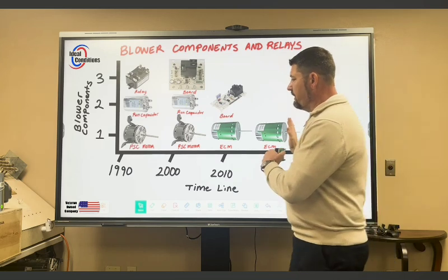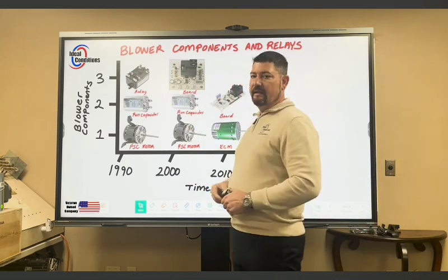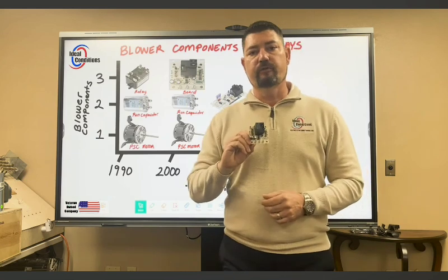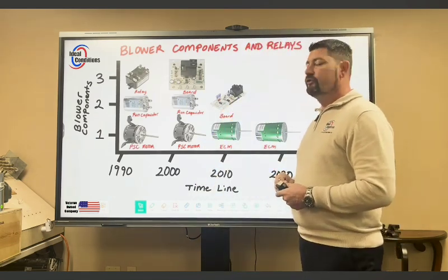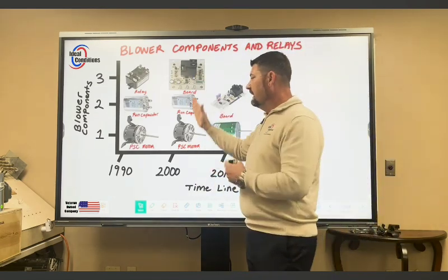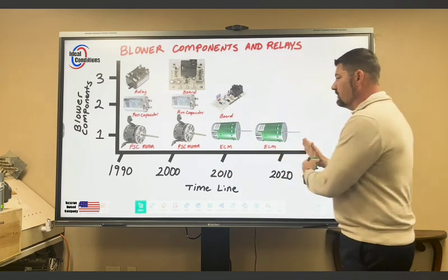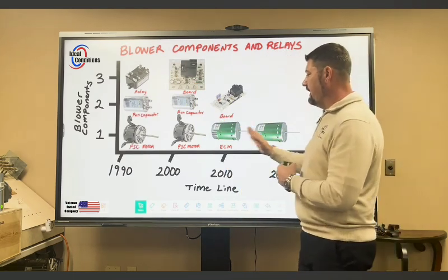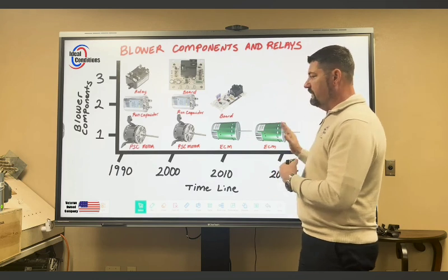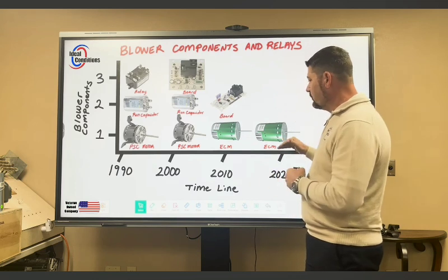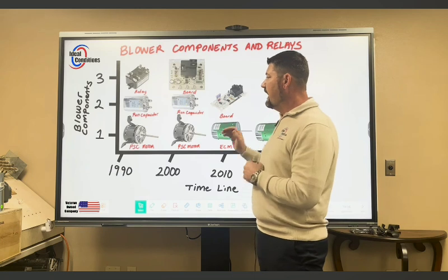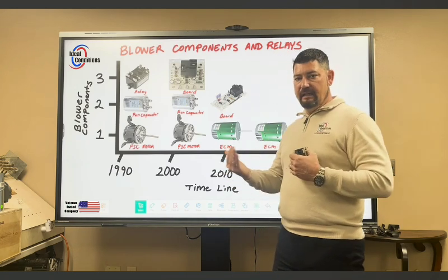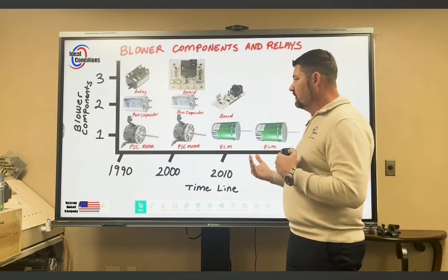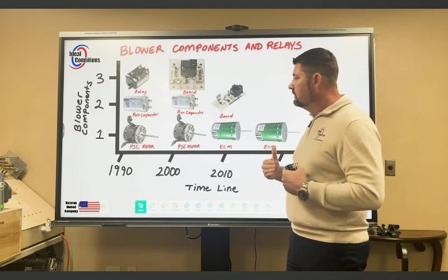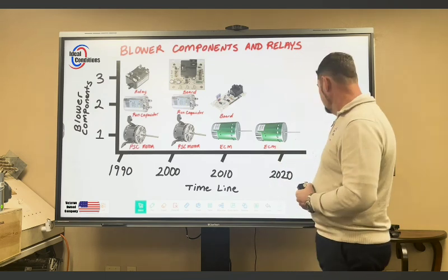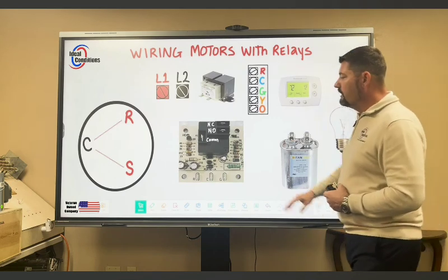And sometimes we have to go back down this timeline, and you may not have a relay. I always recommend carrying at least one blower control board with you if you're still trying to leave it in this condition and still give them the efficiency that they have here. You may not be able to get the same ampacity savings, that lower amp draw on ECMs as opposed to PSC motors. However, you can get that delay and run time on an off cycle and get more efficiency out of that coil. Getting right into it, we're going to go ahead and wire it up.